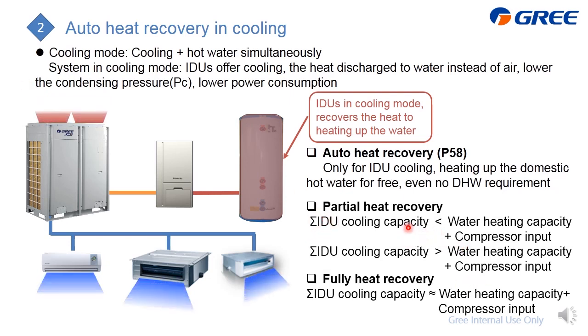And here are some concepts I need to clarify. First is the auto heat recovery, already introduced, which is only for indoor unit in cooling. At this time, there is no domestic hot water requirement. And partial heat recovery, that means indoor unit also in cooling, and at the same time you are on purpose making the domestic hot water. And at that time, the compressor input for this combination can be higher or lower than the indoor unit total cooling capacity. And the fully heat recovery, that means the total indoor unit cooling capacity is almost the same as the sum of the water heating capacity, which is for this one, and the compressor input. At that time, it is fully heat recovery.